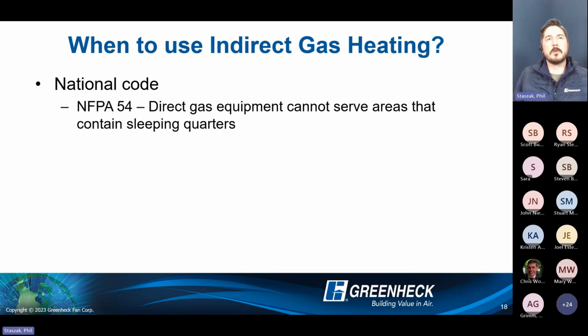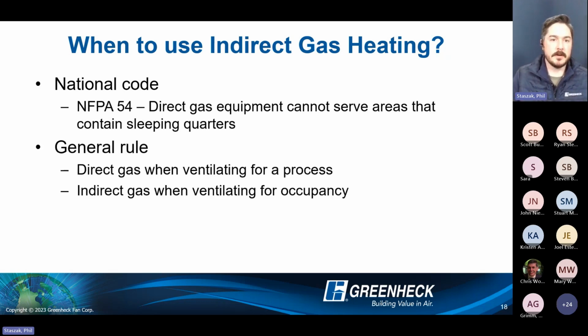But otherwise, sleeping quarters, a good example of this would be a common kitchen area, say in a nursing home, or common living quarters where the kitchen is in the middle of the building and then the sleeping quarters are off of the wings. A firehouse is another great example, or hotel corridor ventilation or stairwell ventilation. Is it part of or connected to a sleeping quarters? That's where you need to consider shifting toward indirect gas fired instead. General rule: direct gas when venting for a process, which is most makeup air applications, and then indirect when venting for occupancy, which is where DOAS mainly comes into play.